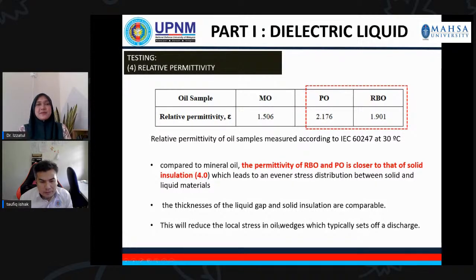And the thickness of the liquid gap and the solid insulation are comparable as compared to mineral oil. So the good thing about a high relative permittivity is that you can reduce the local stress, especially at the wedges of the transformer winding. Normally at the wedges of the winding, you have very high electrical stress. So for vegetable oil, which has a permittivity closer to the insulation material as compared to mineral oil, this will reduce the local stress at that particular area. So it is very good in terms of transformer design. We do not need very thick insulation material at that area, and then we can reduce the sizing of the transformer as well based on this result.